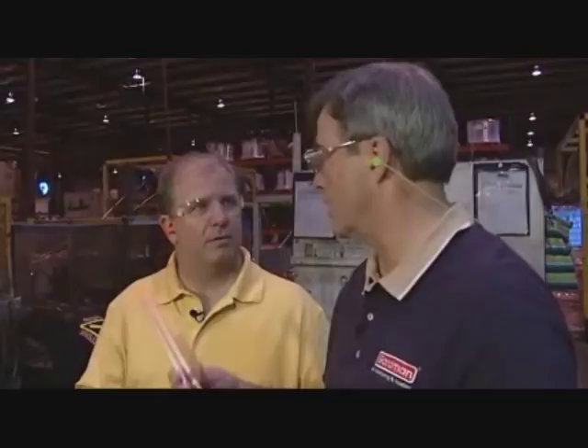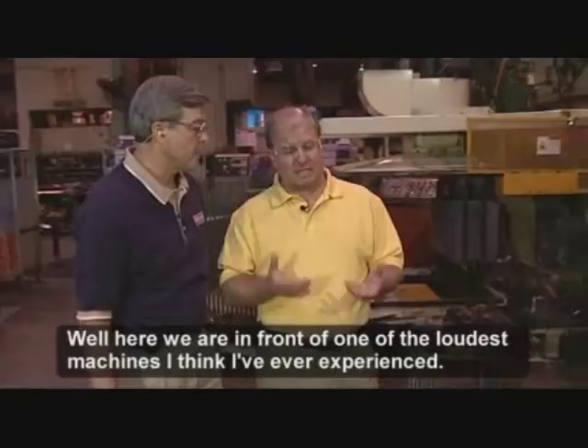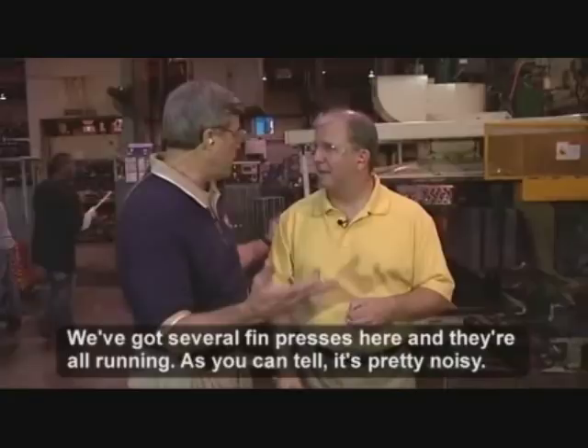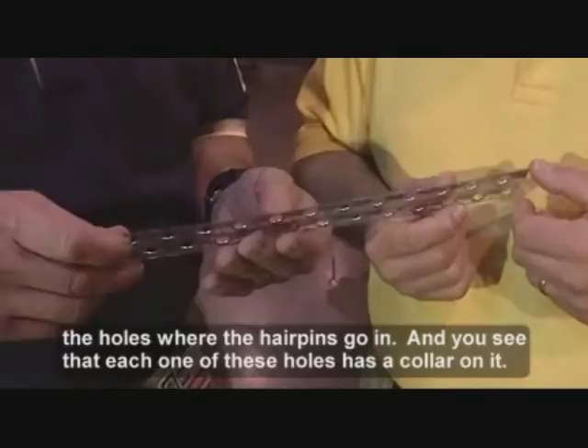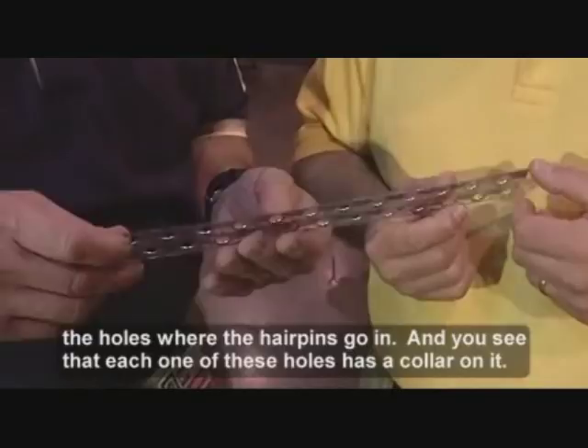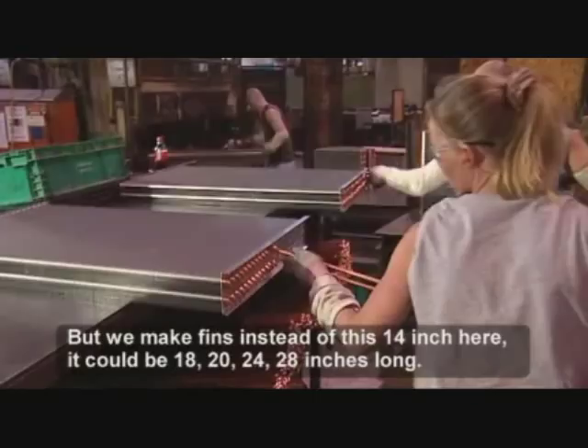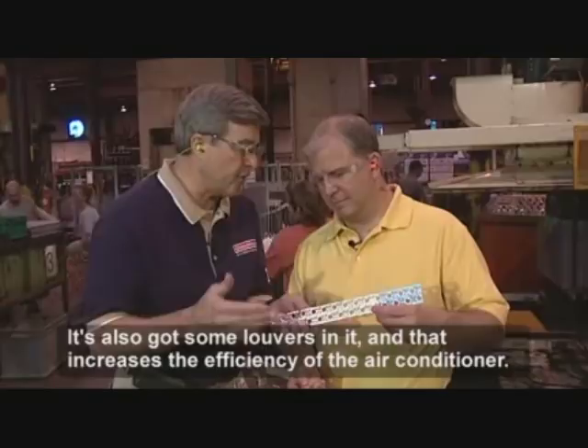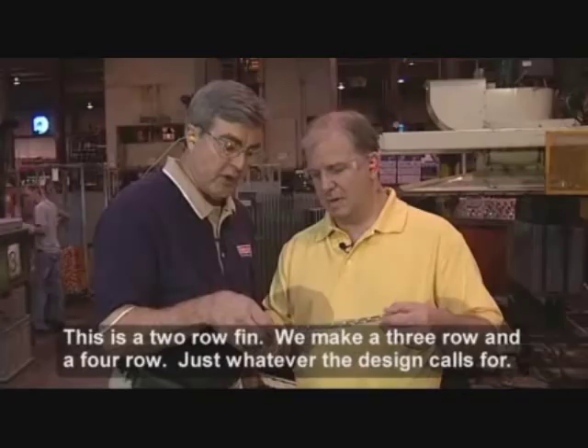Here we are in front of one of the loudest machines I think I've ever experienced. We've got several pin presses here, and when they're all running, as you can tell, it's pretty noisy. What we're doing here is we're stamping the holes where the hairpins go in, and you'll see that each one of these holes has a collar on it. That's how it separates the fins so they don't stack right down on the opposite side. It's also got some loops in it, and that increases the efficiency of the fins. We make fins that instead of 14 inches here, could be 18, 20, 24, 28 inches long. This is a two-row fin — we also make three-row and four-row. It's whatever the design calls for. Let's go take a look at the next step.